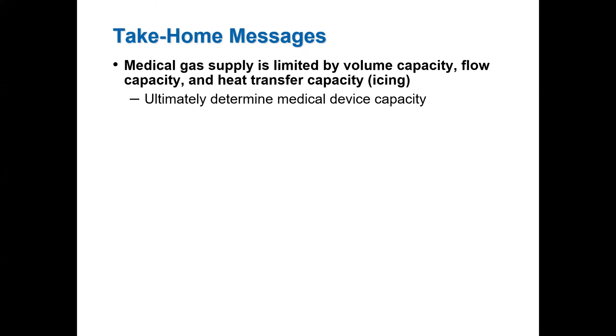The downside of this calculator, though, is they don't share with you the equations on the back end. So there's no way to verify details like, are they talking about BTPS or STPD, which turn out to be significant in high flow rates. So there's something to be considered. So the take-home message, I want to wrap up very quickly. Medical gas supply is limited by volume capacity, by flow capacity, by heat transfer capacity, meaning icing. And all these limitations ultimately determine how many medical devices you can stick on outlets in ICUs.